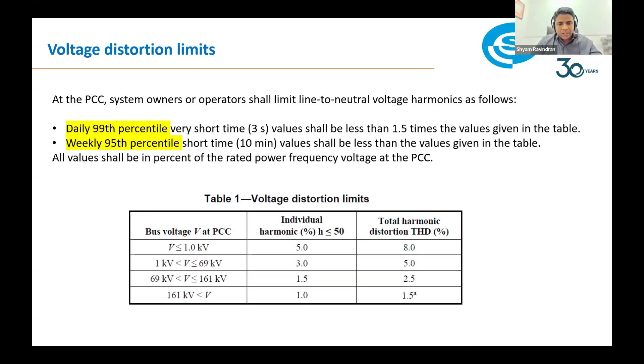From the utility perspective or the end user perspective, the PQ definitions and standards remain the same. But what actually differs between the two is the data—how you actually take the data. Utilities usually go for a fixed or panel-mounted device, whereas end users go for semi or portable devices. Utilities usually ask us for integration with a central PQDMS file for analytics and regulatory reporting, while end users demand software so they can prepare a report. Utilities also look for the PQDIF file format so they can integrate with SCADA. But please note, the data captured by the equipment always remains the same. How you transfer the data, what file extension it has, how you read it, how you put a watchdog function behind it—those are the functions that are changing and evolving rapidly.